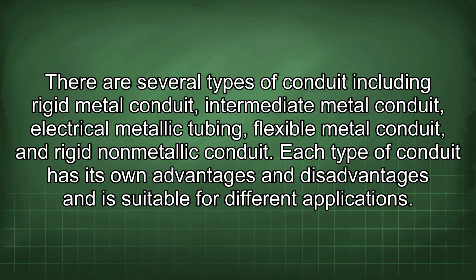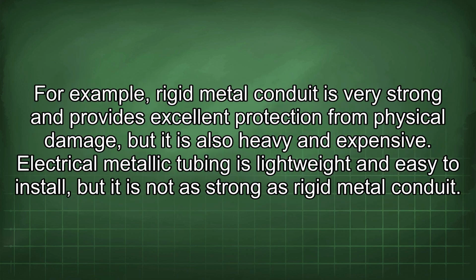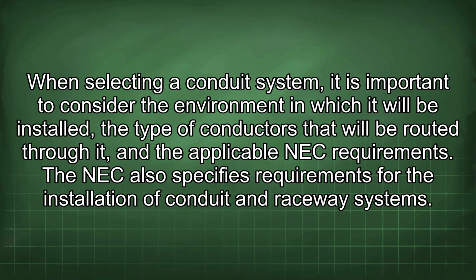Each type of conduit has its own advantages and disadvantages and is suitable for different applications. For example, rigid metal conduit is very strong and provides excellent protection from physical damage, but it is also heavy and expensive. Electrical metallic tubing is lightweight and easy to install, but it is not as strong as rigid metal conduit. When selecting a conduit system, it is important to consider the environment in which it will be installed, the type of conductors that will be routed through it, and the applicable NEC requirements.